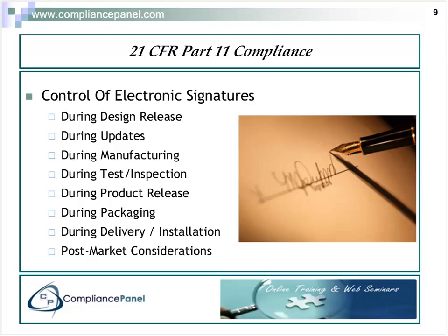And then the post-market considerations at the bottom would be your complaint handling system. I know the easiest method for handling complaints for many companies now is still a paper system, but the FDA is now moving into MDR, where they're going to want to see all the MDRs electronically. That process will be coming through within the next couple of years, for any reportable adverse events, although hopefully most of your complaints are not reportable.